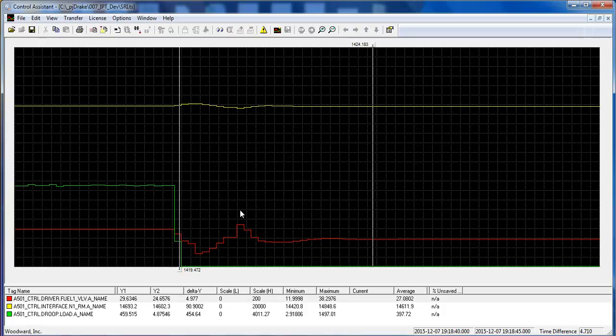This is well below the 57 and 63 hertz trip points and the customer's desired 58 to 62, plus or minus 2 hertz swings that they wanted to achieve. So as you can see, we've had some very good results at the 1.5 megawatt range.